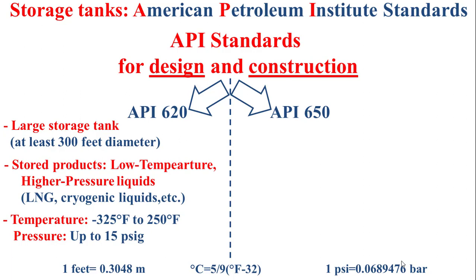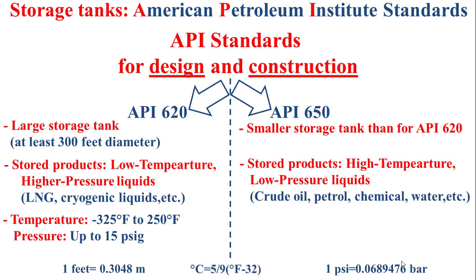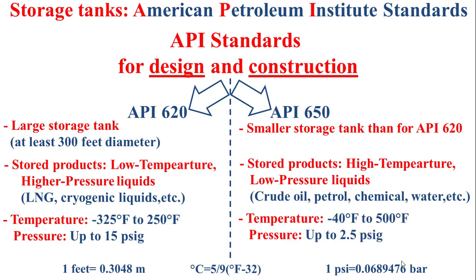For the API 650 standard, it is generally for smaller storage tanks than API 620, and the stored products are high-temperature, low-pressure liquids such as crude oil, petrol, chemical products, and water. The operating temperature is between minus 40°F to 500°F, and the operating pressure is up to 2.5 pounds per square inch gauge.